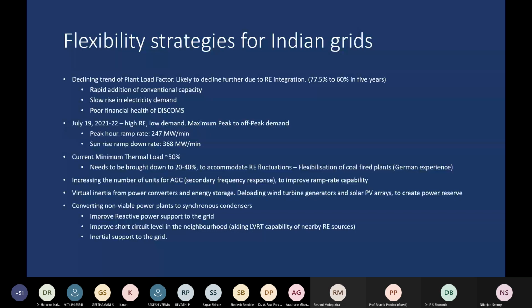There is a lot of experience that can be obtained from coal-fired power plants in Germany and the Netherlands, which are currently, for instance, in Germany, some units of about 800 megawatts can run safely at 90 megawatts, which means almost 10% is the minimum thermal load. And this is not a temporary phenomenon, they should be able to run at minimum thermal load for several hours in a day.